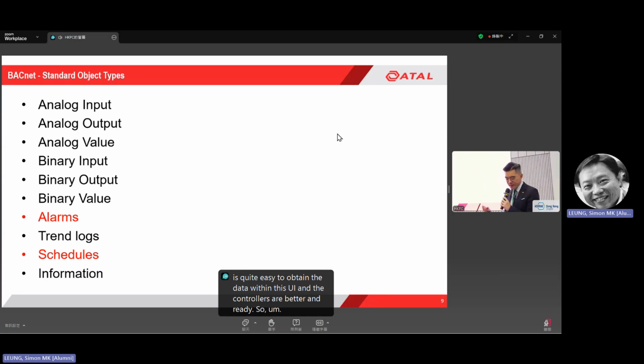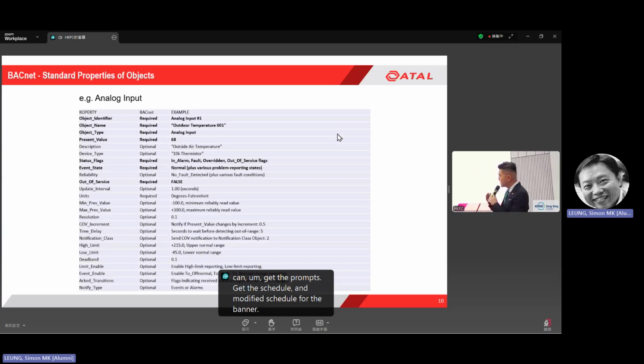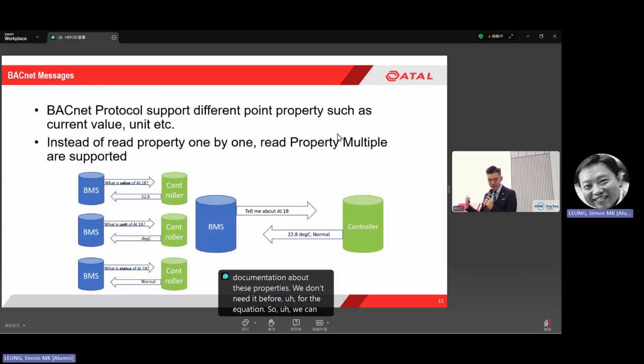So BACnet standardizes the object types. For the analog, binary, alarm, and schedule, that means we can get the points, get the alarm, acknowledge the alarm, get the schedule, and modify the schedule through BACnet. So let's say for the analog input, these are the properties of these objects. All are standardized, so we don't need API documentation about these properties. We know them before the integration. So with BACnet, we can easily obtain the data. Data means the value, unit, and even the status of the point. So this is quite simple.